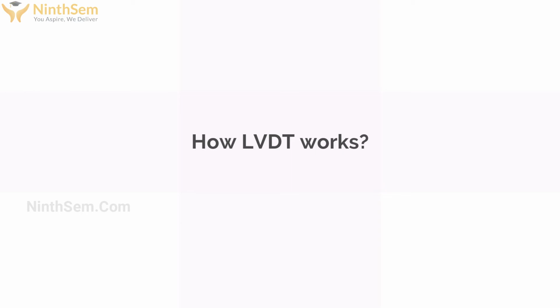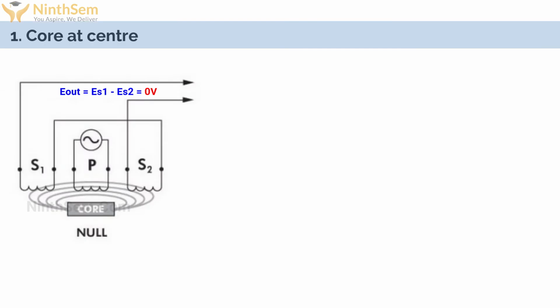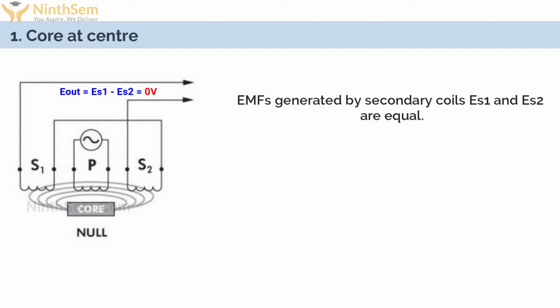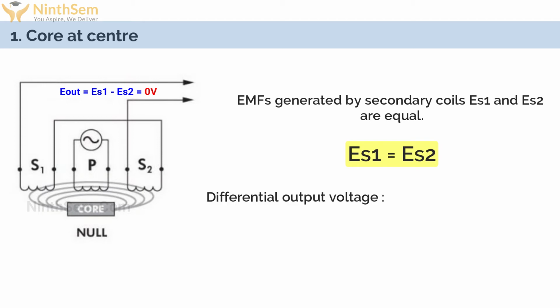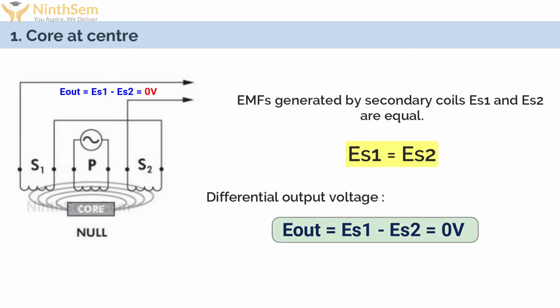Now let's see how LVDT works. As you can see in the figure, when the core is at the center, the magnetic flux generated by the primary coil linking with the two secondary coils is the same. So the EMFs generated by the secondary coils, ES1 and ES2, are equal. Hence we get the output voltage E output equal to ES1 minus ES2, which is equal to 0. So this position is called the null position. That means there is no movement of the core inside the hollow former.